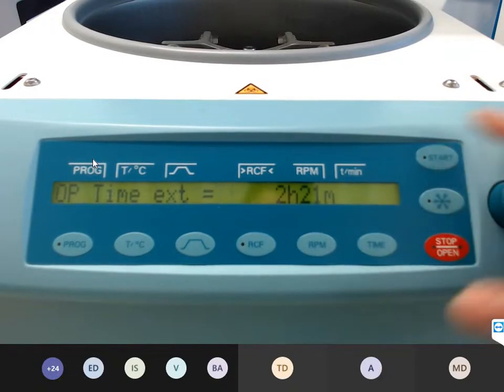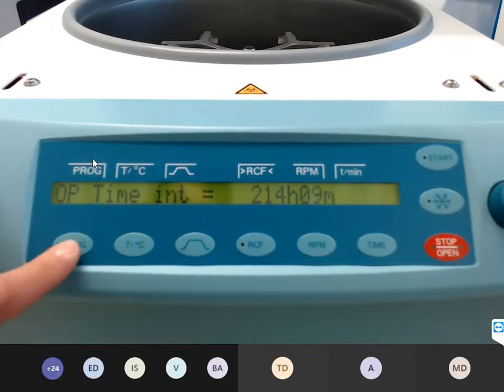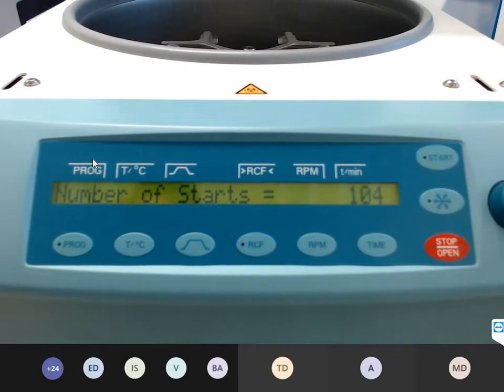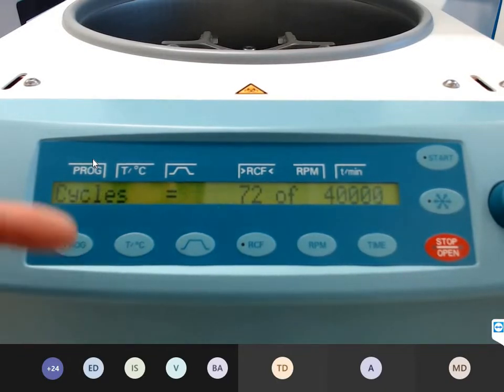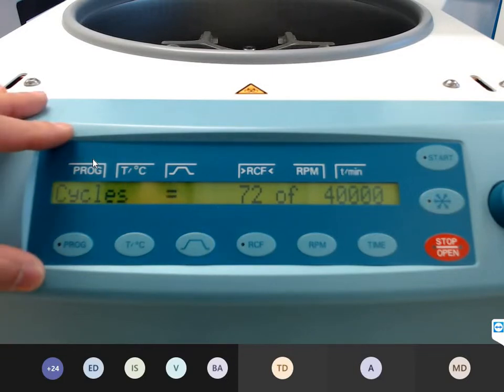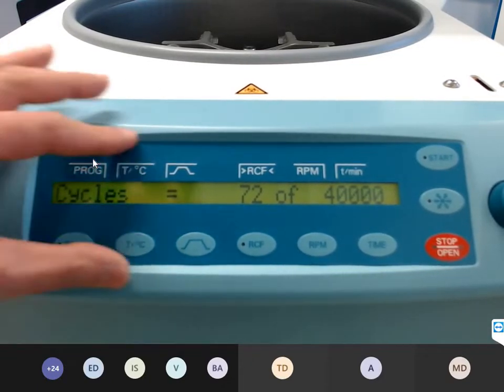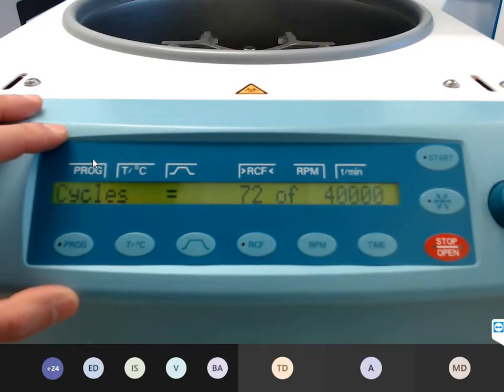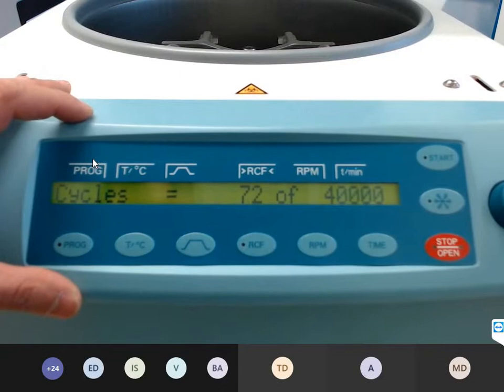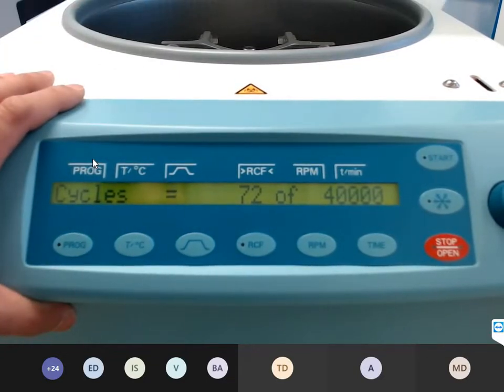Important thing, the operating time, externally and internally. You will find in the sales manual the description of the externally and internally time, what means externally and what means internally time, the numbers of starts, the cycles, very important. You can set the cycles. We have here a cycle counter. If the centrifuge reaches the cycles, you get here an error message. It means maximum cycles passed. In this case, you have to change the rotor or the buckets.